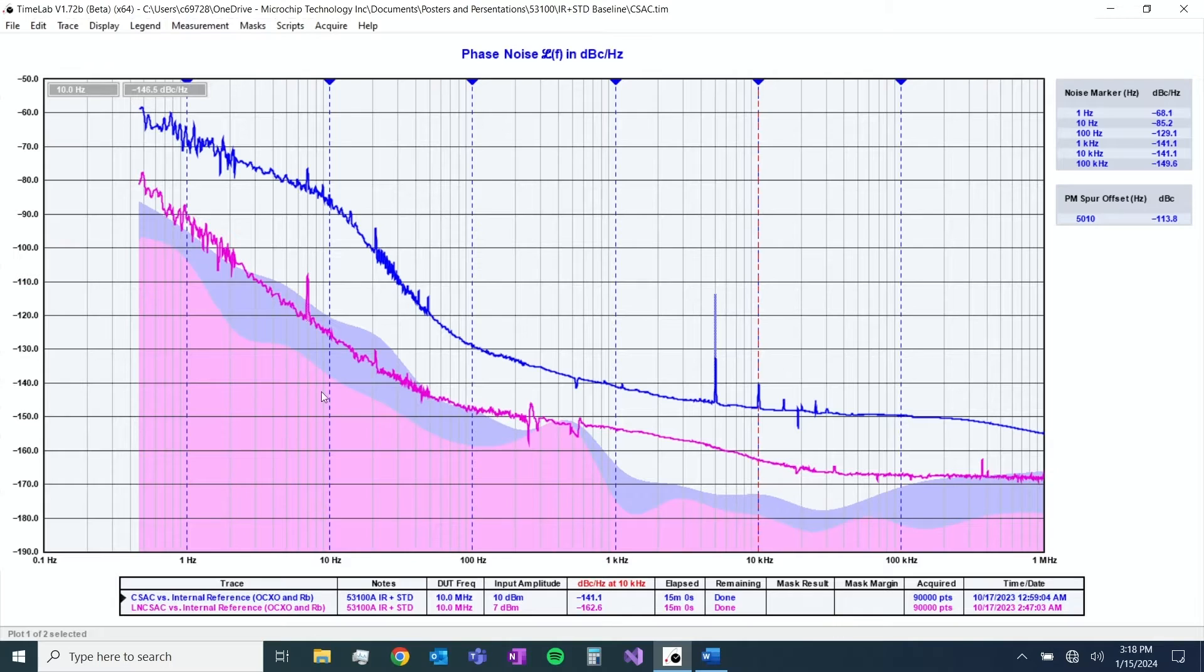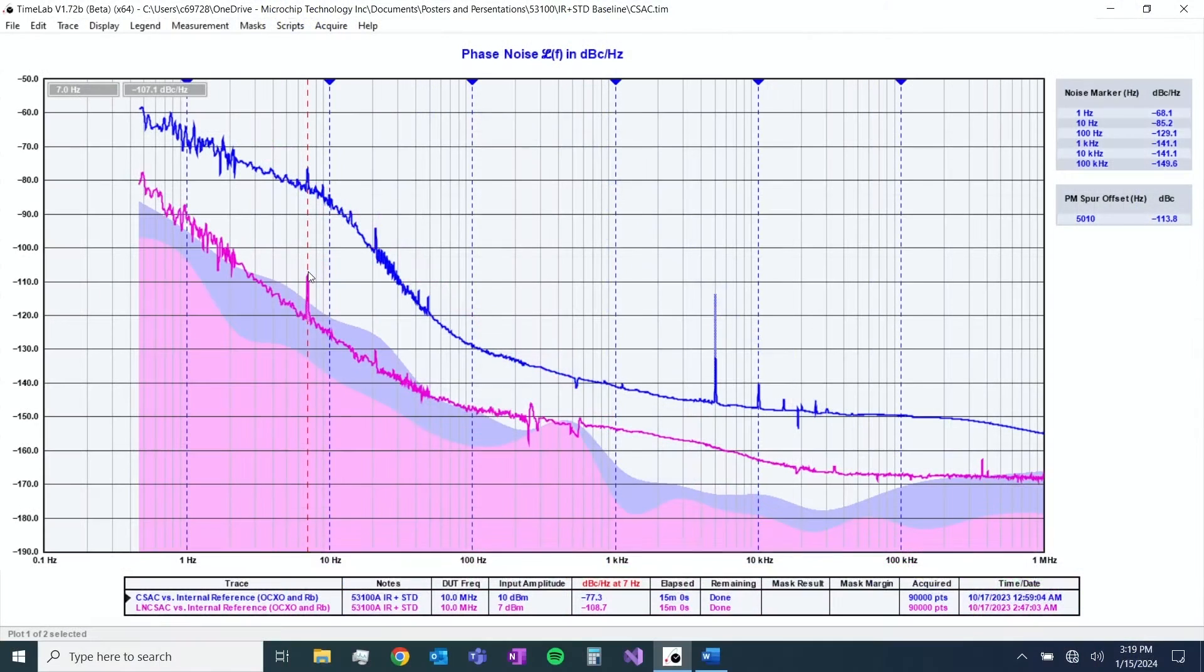But if you get really close to the carrier say around this 10 hertz bandwidth you'll start to see things that are present in the system, say this spur here at 7 hertz is actually intrinsic noise to our device under test. So maybe you want to mark that, come back to it later, use some other analysis techniques to find out where these frequencies in your system are popping up. Another really powerful tool that this view gives you is the ability to measure jitter. If you work in the time domain you'll work with jitter a lot more than phase noise but let me show you how to pull that up here.